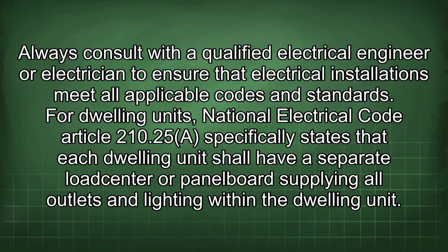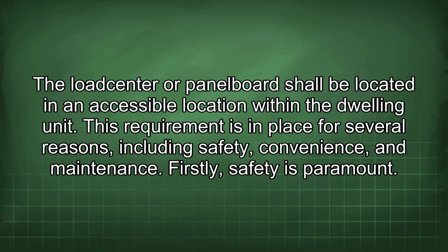For dwelling units, National Electrical Code Article 210.25 specifically states that each dwelling unit shall have a separate load center or panel board supplying all outlets and lighting within the dwelling unit. The load center or panel board shall be located in an accessible location within the dwelling unit. This requirement is in place for several reasons, including safety, convenience, and maintenance.